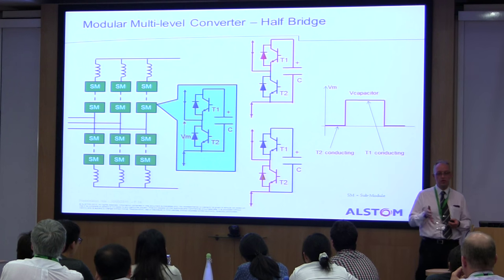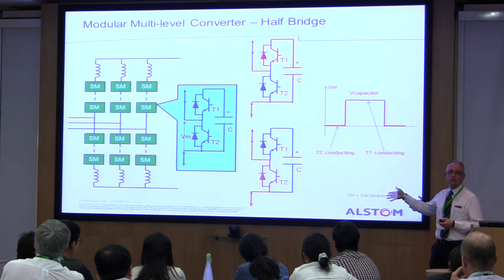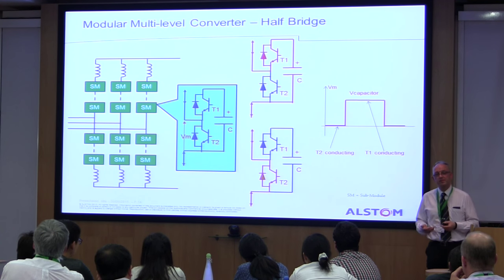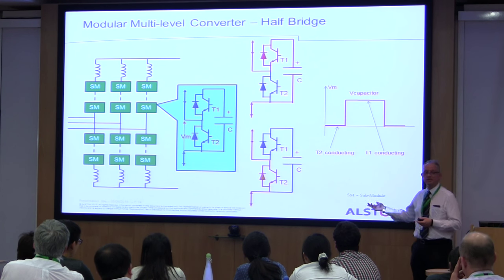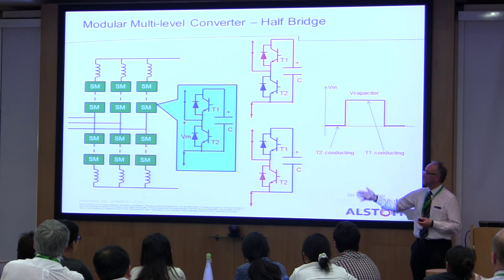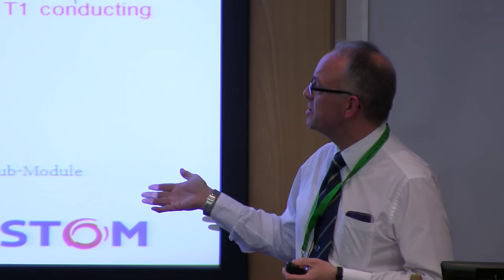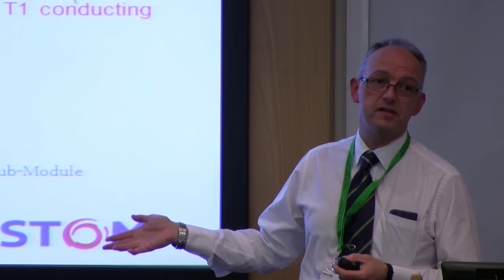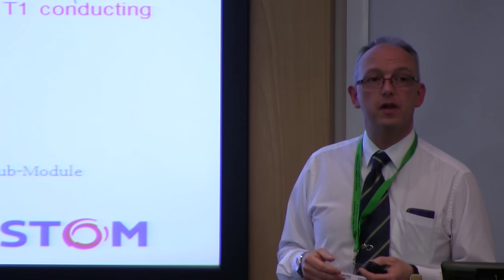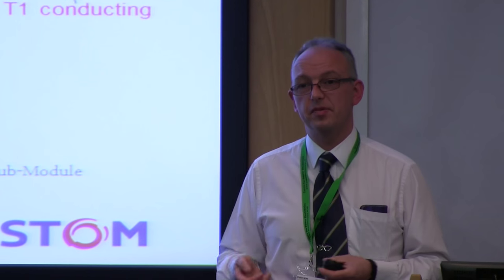So now modular multi-level converters using series half-bridge submodules interconnected becomes feasible. At this point we're talking about losses going from four or five percent down to about one to one-and-a-half percent when this was first introduced ten years ago, now down to one or just below one percent with improved technology. That compares with LCC technology where we're at about 0.7% losses.